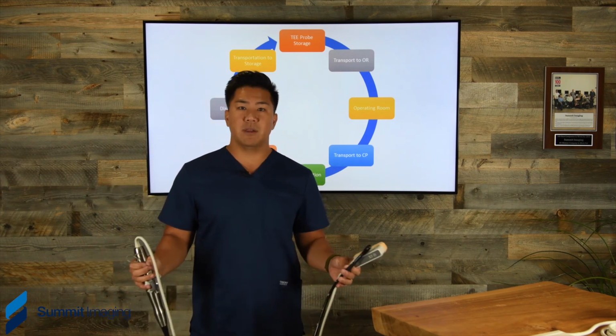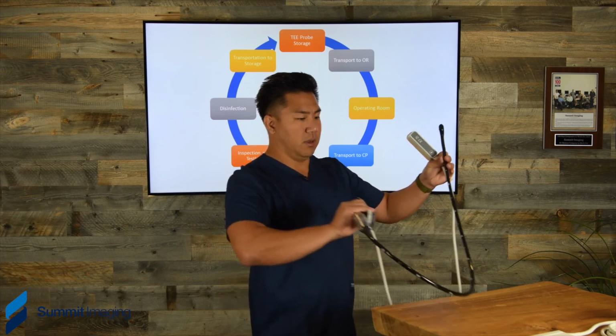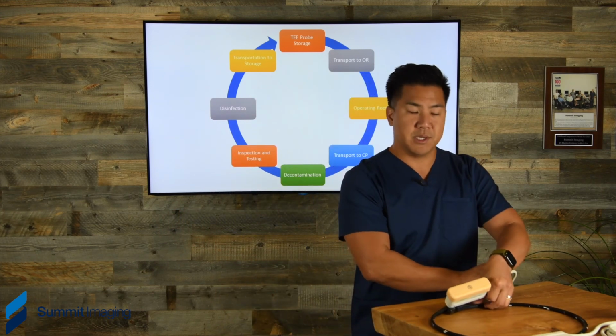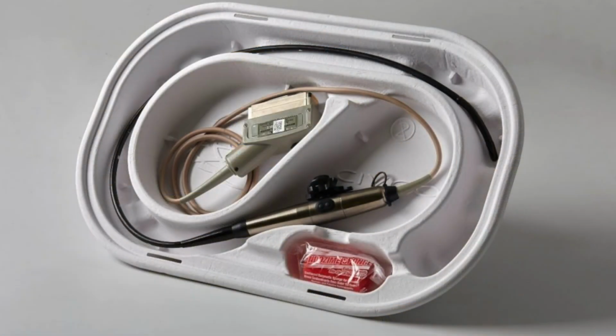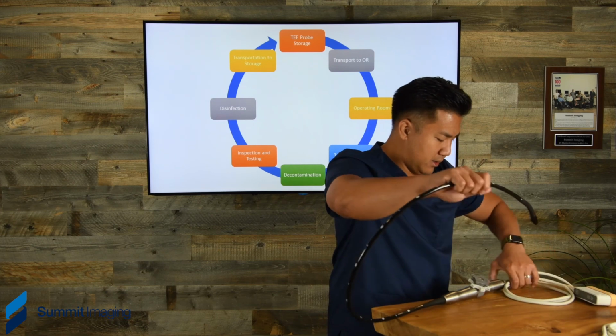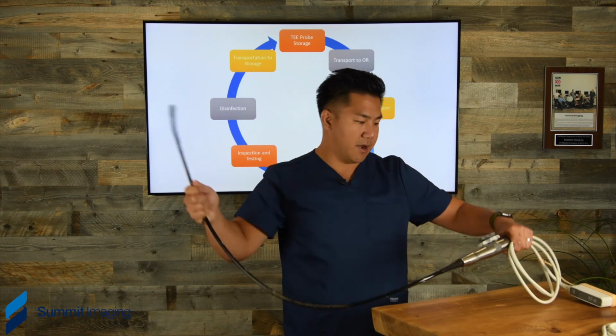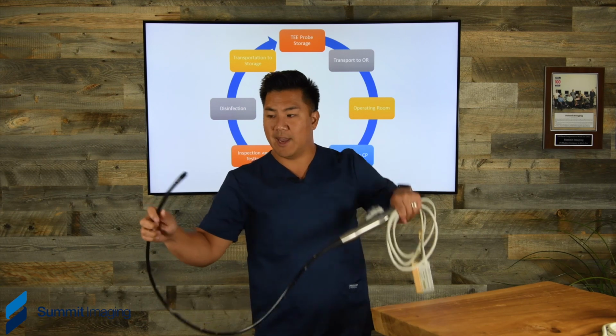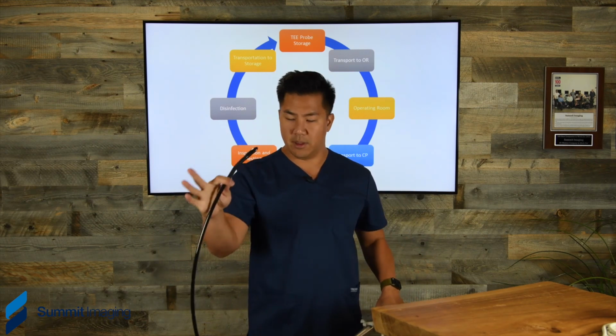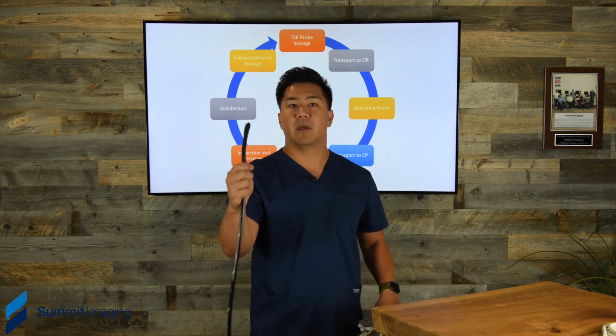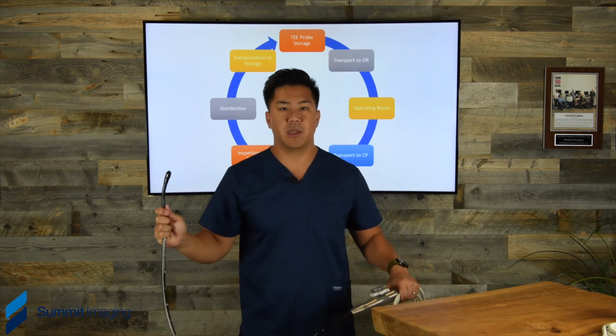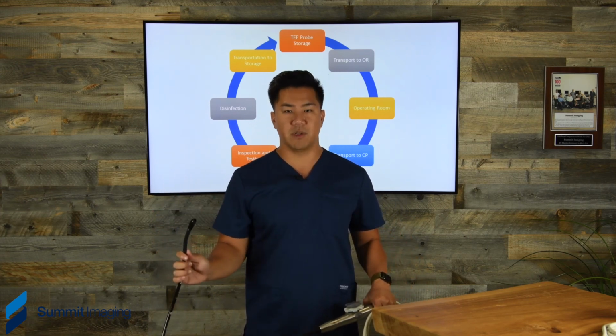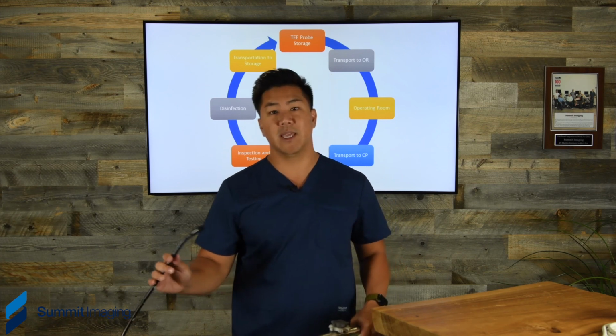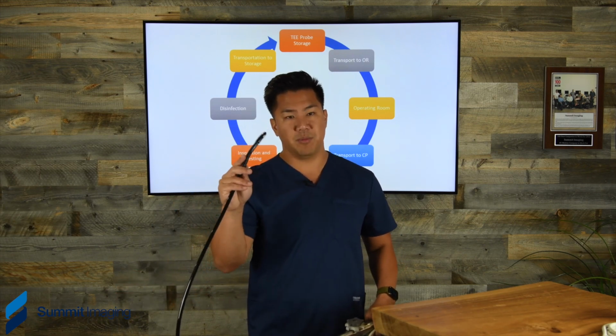So what do we recommend? We recommend getting a proper transport box for this. We've seen some nice totes, but if you really have to, we really recommend coiling up, grabbing the handle, coiling up the cable, and now holding this right underneath the tip with some gloves. And this is a way to control all the heavy parts of this transducer, because the heavy parts are what's going to hit things, especially protecting this tip.